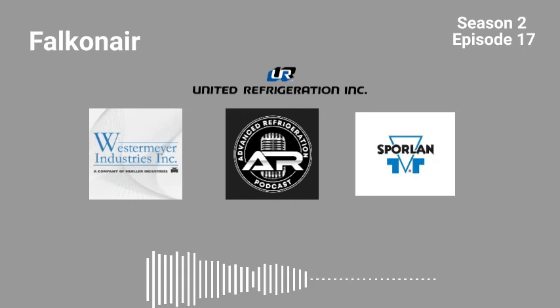Is there any way to use the Modbus points on that to integrate it to the EMS controller on site? It seems like that would be something a customer would want, especially in a supermarket application. These customers are all data driven. It seems like it would be a huge thing for them to be able to integrate with Emerson or Danfoss or Novar, or RDM, to pull those data points out and bring them back to the actual home controller for logging and easy access.